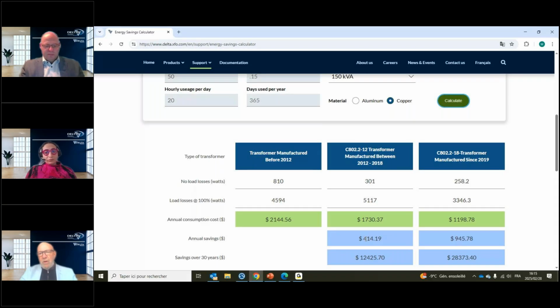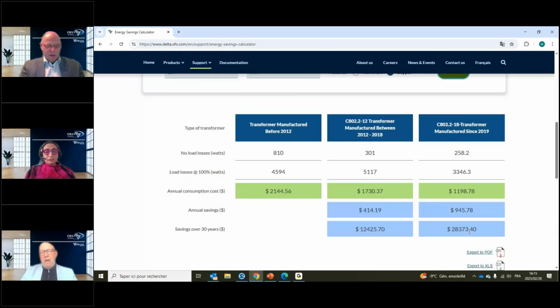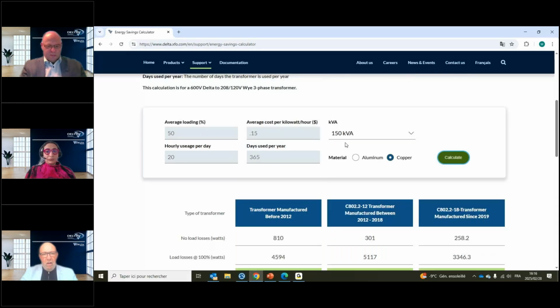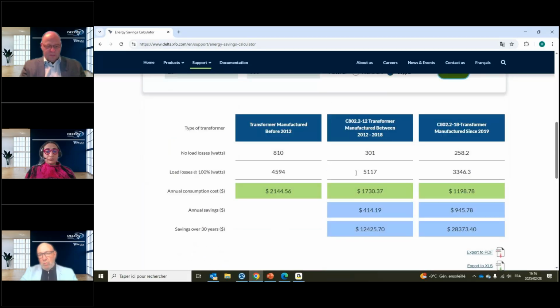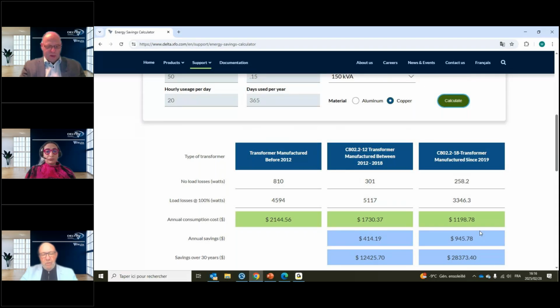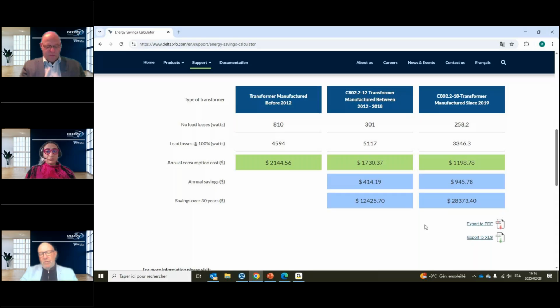And if you use a copper transformer under the efficiency standard C802.2-18, which has been in place since 2019, then you save almost $1,000. Over 30 years, we put the savings over 30 years because the average life expectancy of a transformer is more or less around 30 years. That provides you an overall saving over that period of time. So as you can see, just one 150 kVA transformer loaded at 50%, you can save $28,000 over the life of the transformer. So it's pretty easy to calculate your return on investment by replacing the transformer.